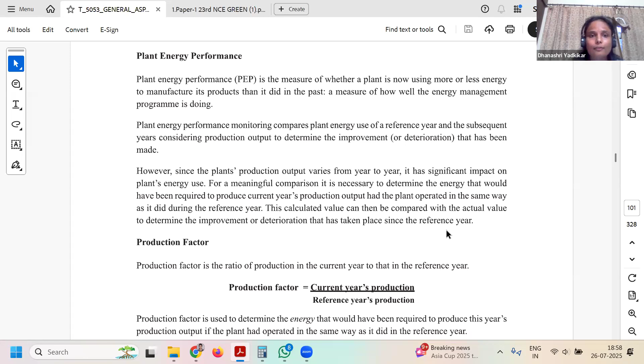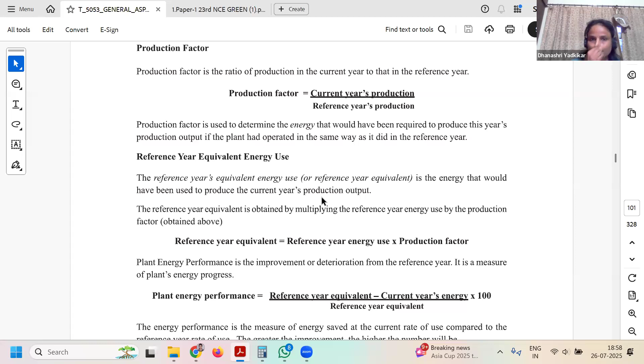However, since the plant's production output varies from year to year, it has a significant impact on the plant's energy use. For a meaningful comparison, it is necessary to determine the energy that would have been required to produce the current year's production. So first is the production factor. The production factor is the ratio of the current year's production to the reference year's production. Then the reference year equivalent energy use is the energy that would have been used to produce the current year's production output. It is the product of the reference year's energy use and the production factor, because it refers to the current year's production also. Then plant energy performance is the reference year equivalent minus the current year's energy, divided by the reference year equivalent.